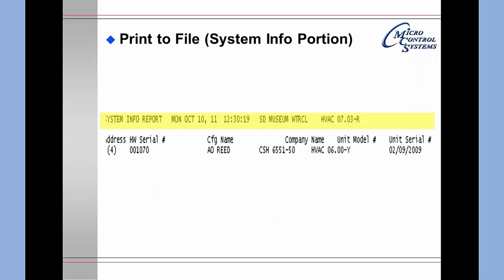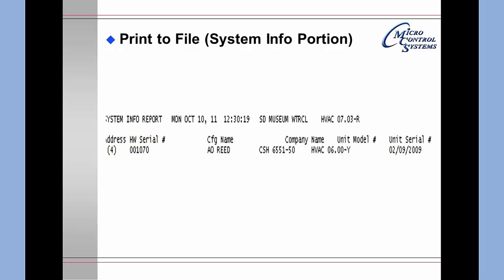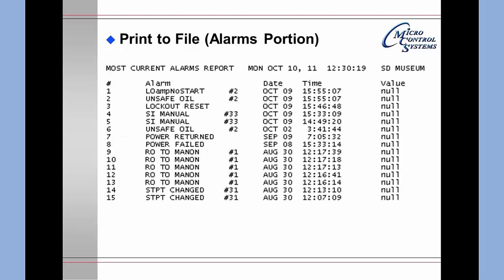The following pages show control status, set points, alarms, etc. This is an expansion of the header portion, which shows that this data was pulled on Monday, October 10th, 2011 at 12:30 in the afternoon. It is from the San Diego Museum and we're currently running HVAC 0703R. There are 100 alarms stored in the Magnum and I have printed out just the first 15 so they are large enough to see on the screen.